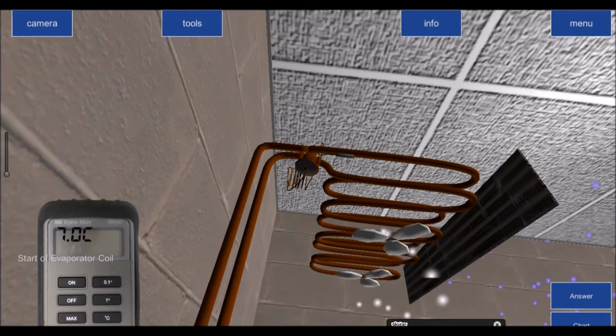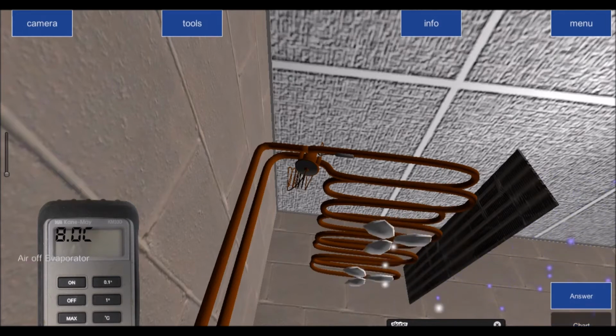So, because it's 3 degrees of a difference, and it should be between 5 to 10, so a minimum of 5 degrees lower, maximum of 10 degrees lower, in our case it is 3 degrees lower. So when we look at this, we have to ask ourselves, is it too low, is it normal, or is it too high?